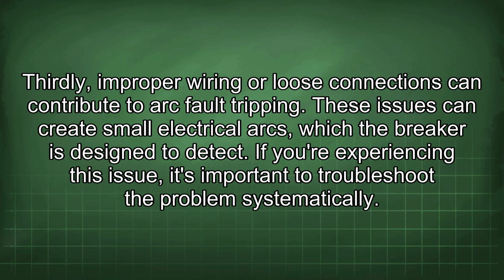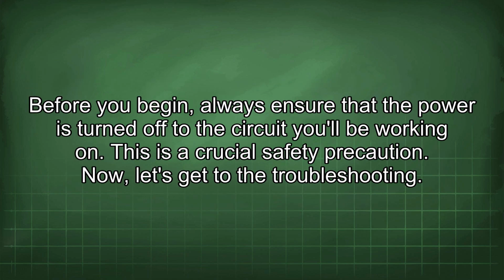Thirdly, improper wiring or loose connections can contribute to arc fault tripping. These issues can create small electrical arcs, which the breaker is designed to detect. If you're experiencing this issue, it's important to troubleshoot the problem systematically. Before you begin, always ensure that the power is turned off to the circuit you'll be working on. This is a crucial safety precaution. Now let's get to the troubleshooting.